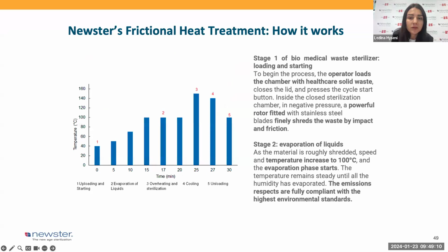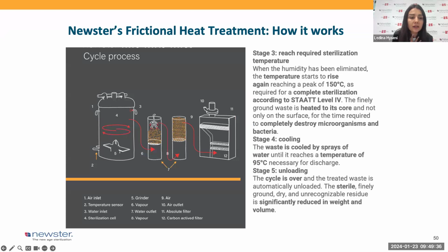Here we have the different stages of the cycle. Stage 1 is the loading and starting of the machine, where the powerful rotor shreds the waste by impact and friction. Then we have the evaporation of the liquid as the second stage. The temperature starts to increase, and the emissions are fully compliant with the highest environmental standards. Stage number 3 is the moment where the sterilization point is reached, with a peak of 150 degrees required for a complete sterilization according to STAATT level 4, to completely destroy microorganisms and bacteria contained in the medical waste.